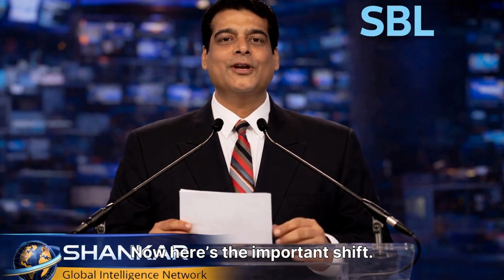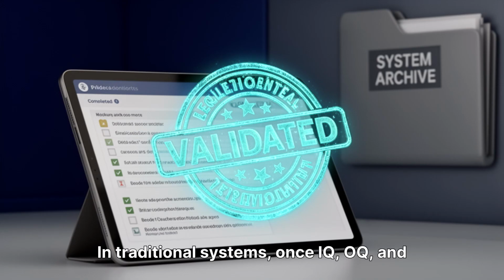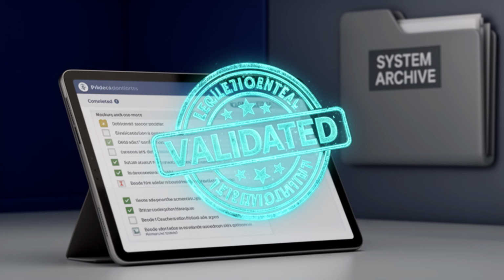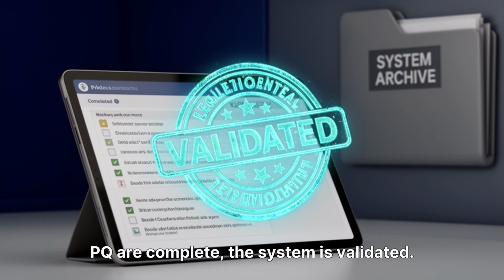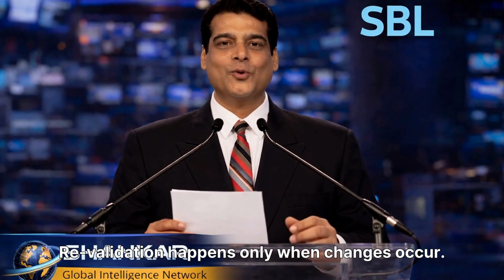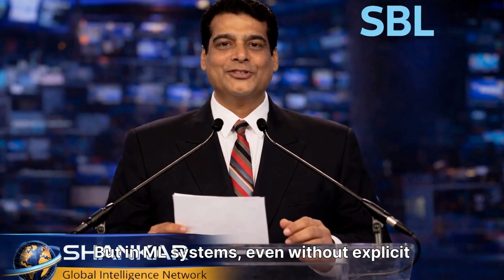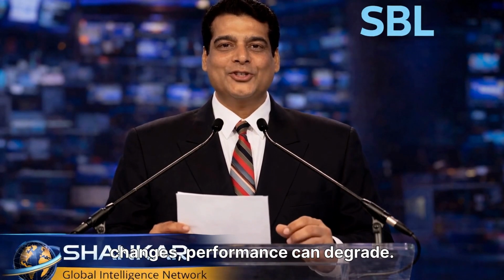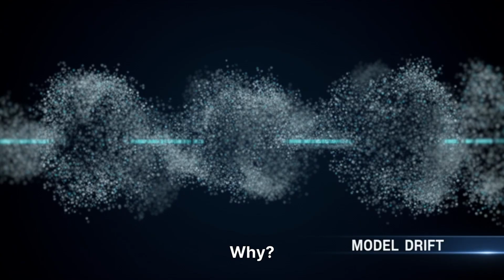Now here's the important shift. Machine learning introduces something new, continuous validation. In traditional systems, once IQ, OQ, and PQ are complete, the system is validated. Revalidation happens only when changes occur. But in ML systems, even without explicit changes, performance can degrade. Why? Because data changes, data evolves, new patterns emerge. This leads to model drift.